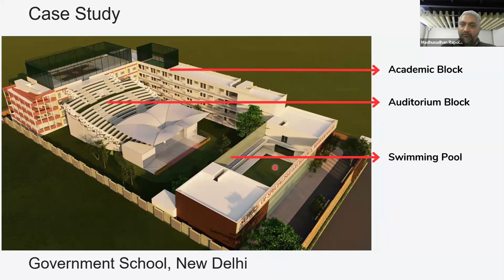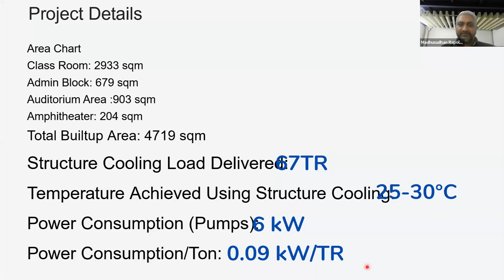For such a building, since there are only two pumps being used for cooling, your consumption is only 0.09 kilowatt per ton. And by the way, I'm not saying that this will provide 24 degrees, 50% RH kind of comfort, but this will provide comfort that is sufficient for a public infrastructure building of this kind. So I just wanted to share that technology like this is available. There's no patent or anything anybody has. Those interested can design this and implement it. These are much simpler than most other technologies in the HVAC industry.